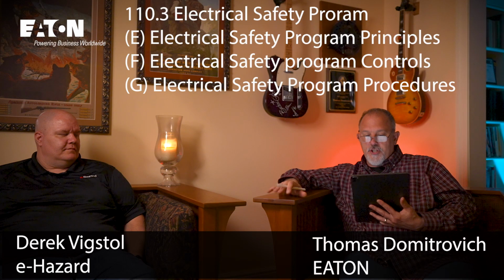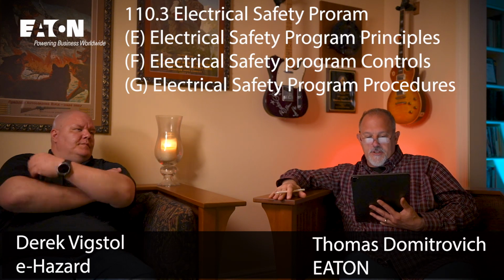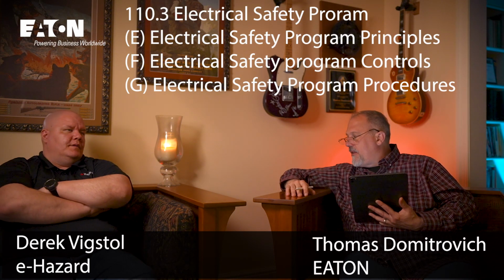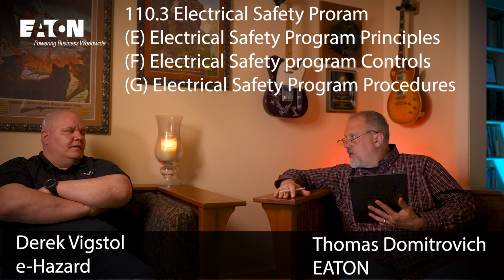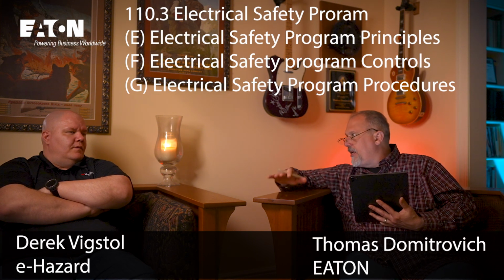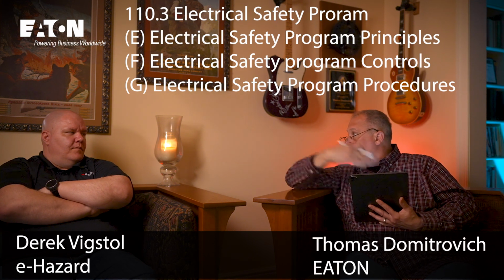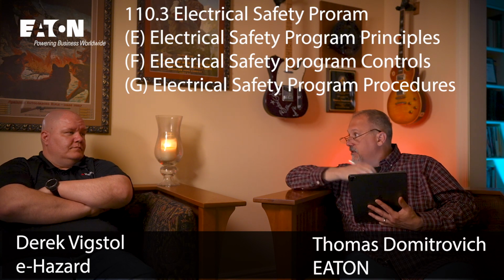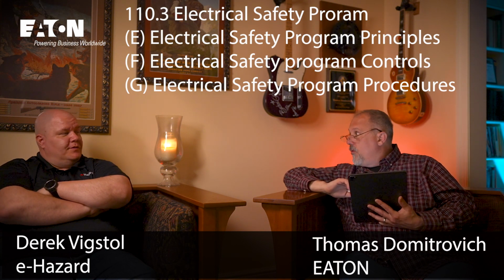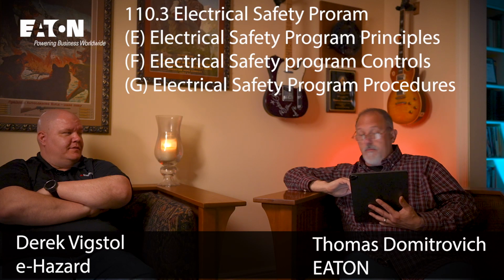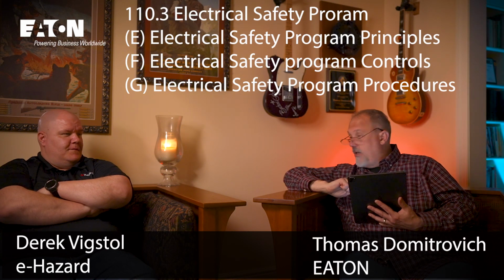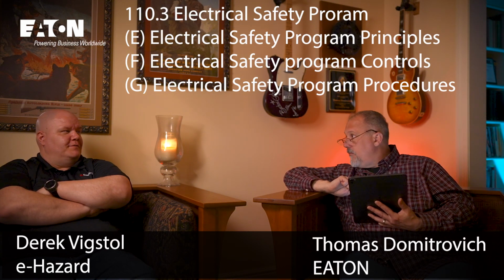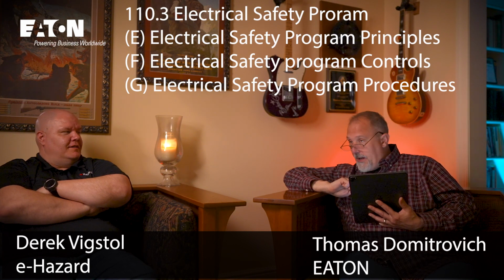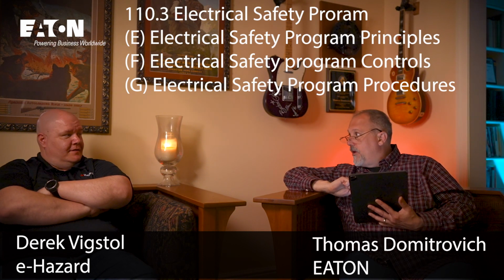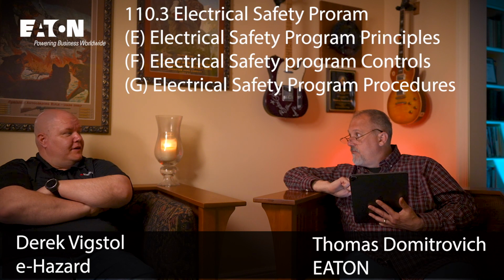Protecting employees from electric shock, so that's your protection, that could be anything. That could be anything of reducing the blast, wearing PPE, giving them the tools to work outside the arc flash boundary. There's a lot of things. Designing my system so that there's tools in place to make sure that they, or energy reducing maintenance switches, zone selective interlocking, all those technologies, active arc flash mitigation.